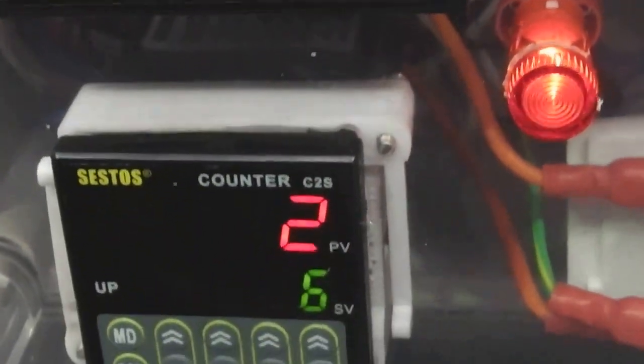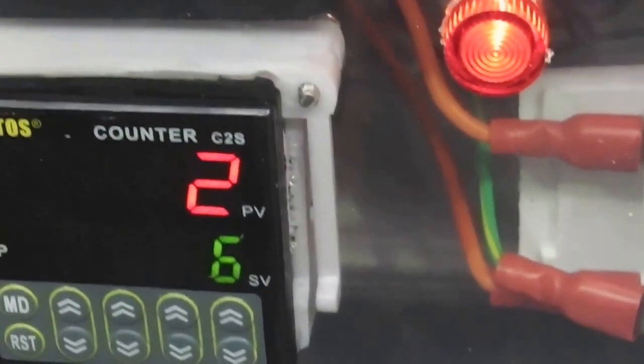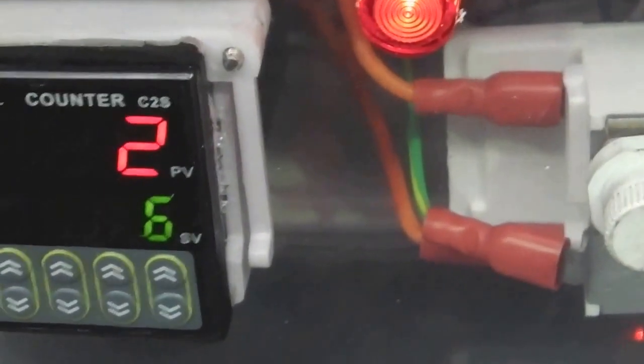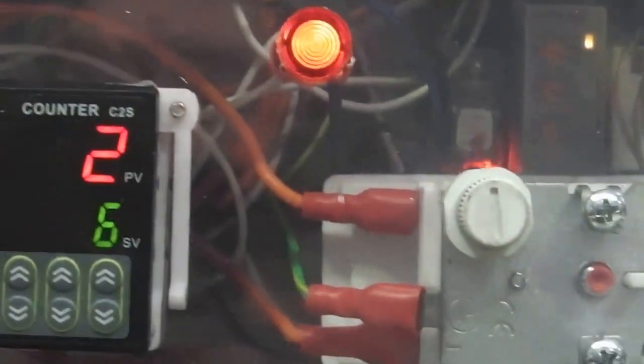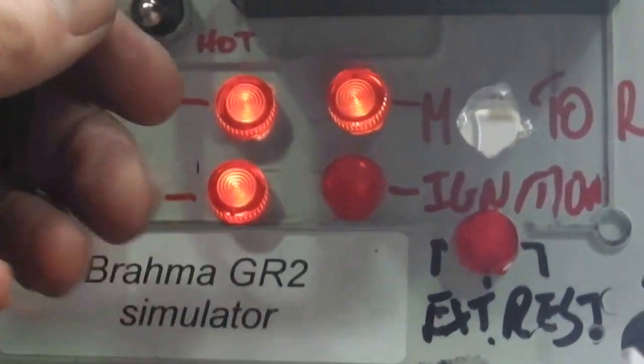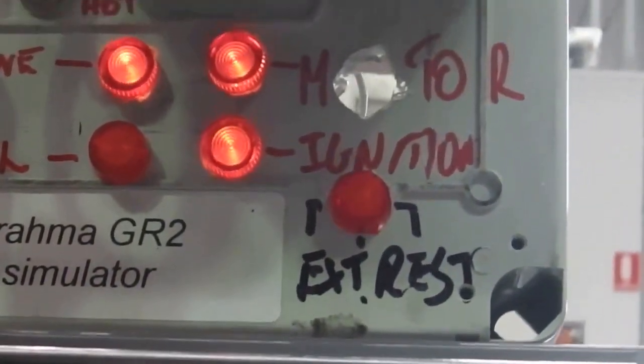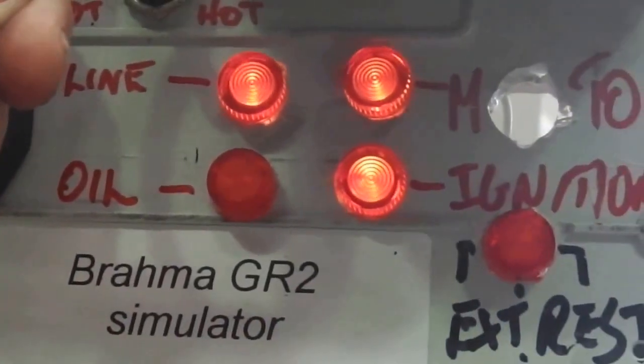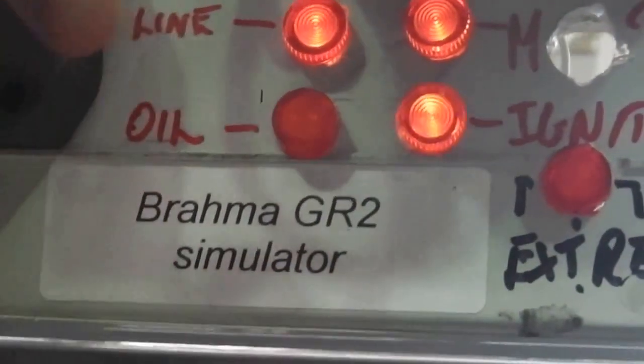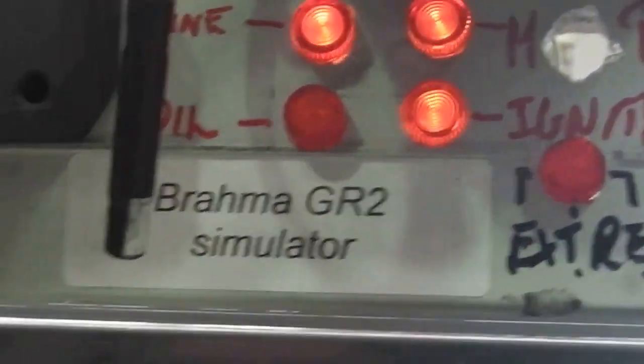So again, this time looking down the bottom, the Sestos counter is on 2, so that means it'll just have 2 more resets, and then it won't do any automatic resets anymore. So looking back up the top here, we'll force it to go into a fail mode. So the oil stopped as soon as I did that. And what I'll do is I'll take my hand off the photoelectric cell and we go into a flame failure and the cycle starts again.